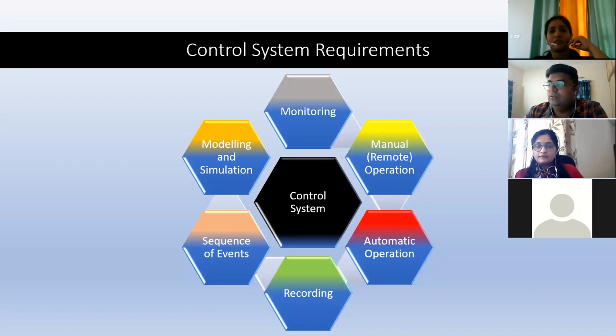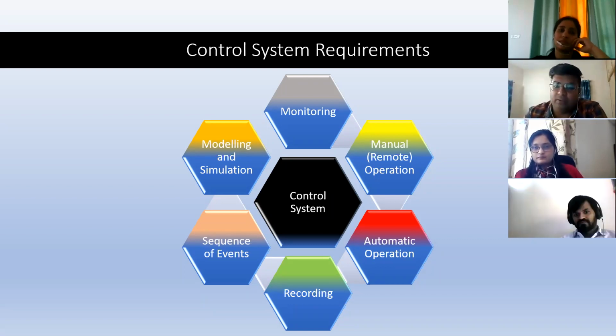So if there is some failure, you have the recorded data to analyze, the trends to analyze how that system responded before the failure. Then, based on experience and based on the work done by the system earlier, you tend to reach out to a root cause analysis. You do a fishbone analysis and see why that system failed - is it something very local, or related to the device itself, or the process itself? You go and analyze, and what enables you to do that is the monitoring and recording system provided by the control system.